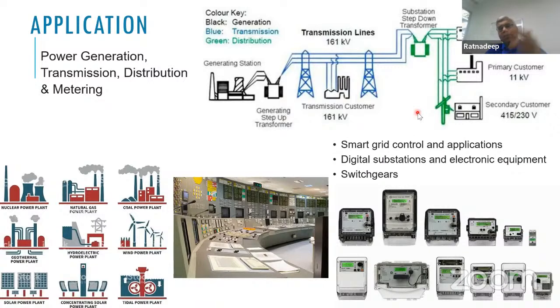You can prioritize the messages that go through. Ethernet is not actually a real-time protocol - you just broadcast, and you cannot predict at what time it will reach the destination. But it is the best medium. So they have formed a separate protocol for industrial application, the IEC 61850, and this has requirements on both sides.